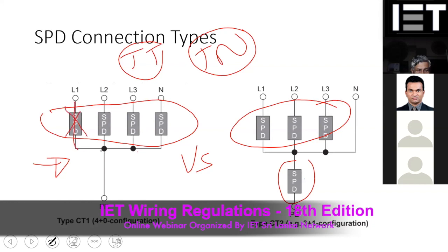So there is a connection like this, and it will go to earth. But in a TT, this is going through the ground return, where you have a very high loop impedance. So what will happen? Will the overcurrent protective device detect this type of situation?